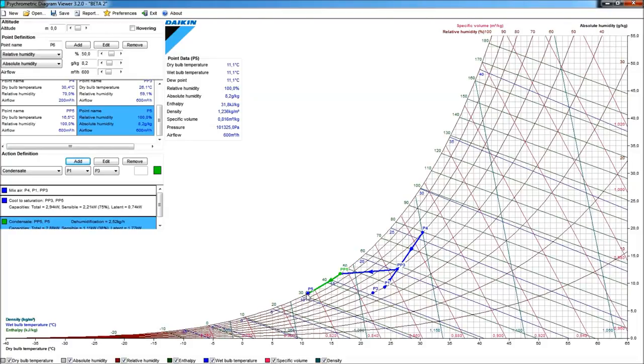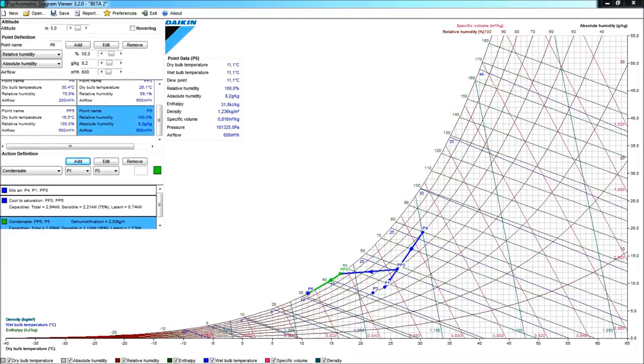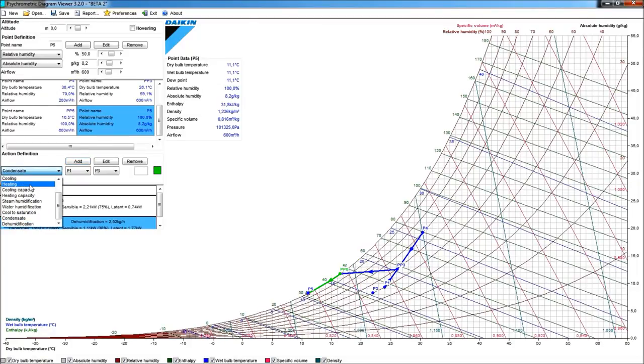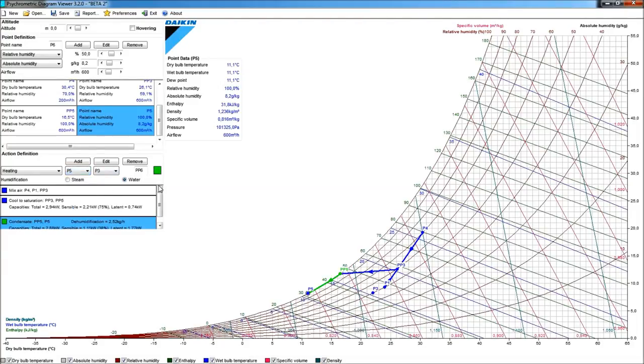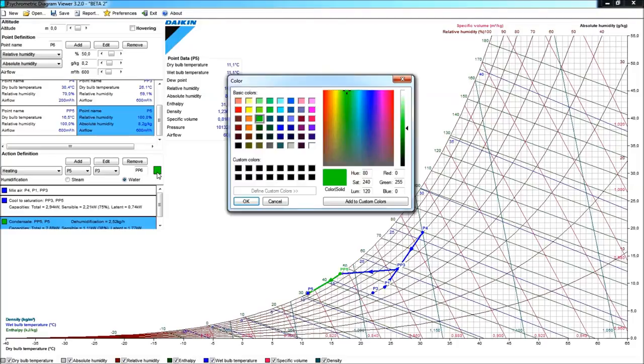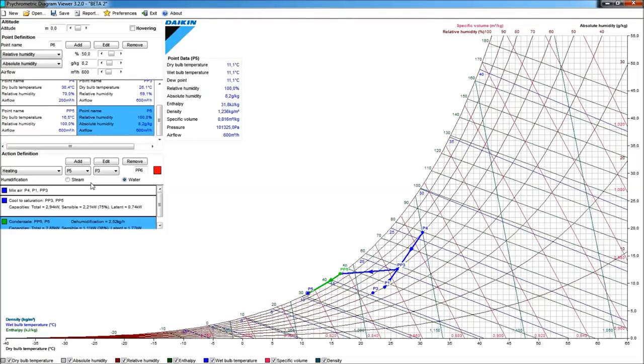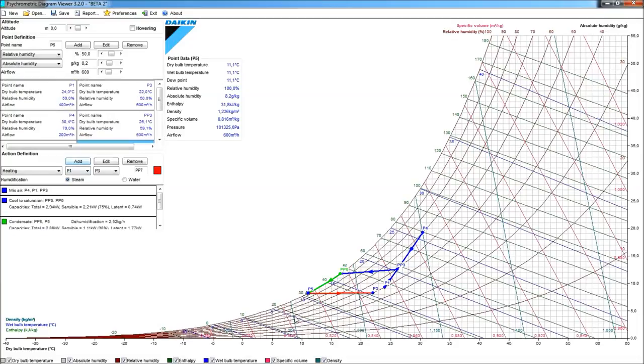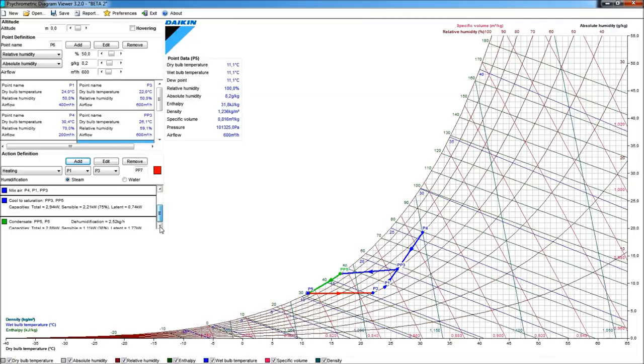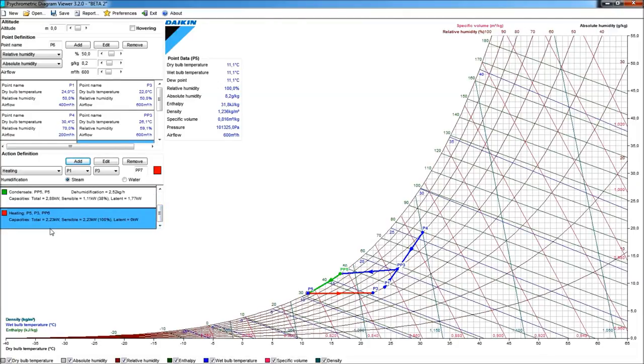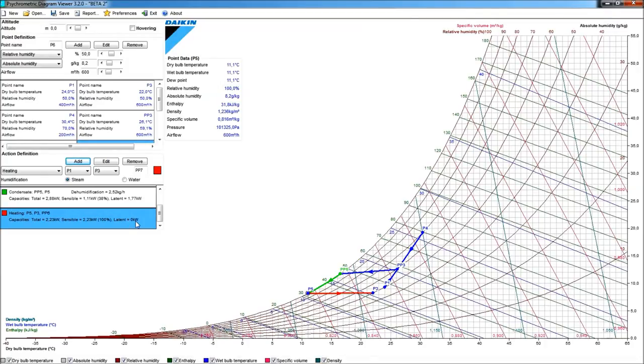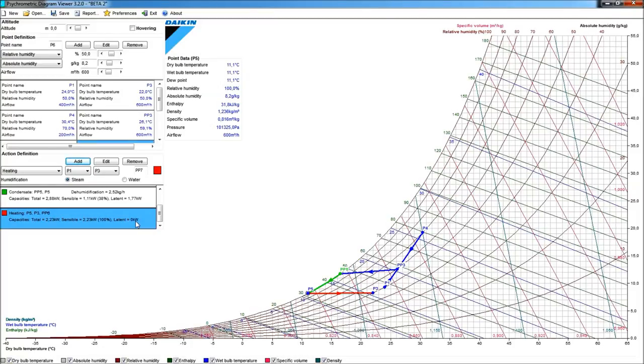What I can do now is to add heat, sensible heat, to get to the condition P3. So, what I still would have to do now is to add another action, another action where we will heat, we will heat between the point P5 and the point P3. I'll give that a red color. Okay, and when I add this, we see that it is a pure horizontal line, fully horizontal line to P3, so only sensible heat is given, and this is what we also will see in the label. We have a total capacity of 2.23 kilowatt, out of which 2.23 are sensible, and nothing is latent heat. Okay, this is how I specify this cooling from PP3, my mixing condition, to my room desired condition. Now, what we can also show here now, is a function to see everything much better, because if we want, we can zoom in to the diagram, simply with the wheel mouse.